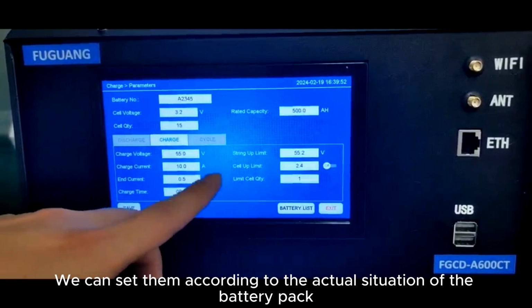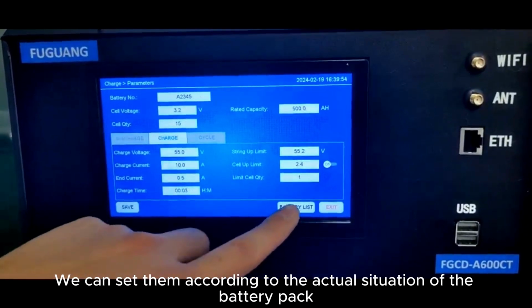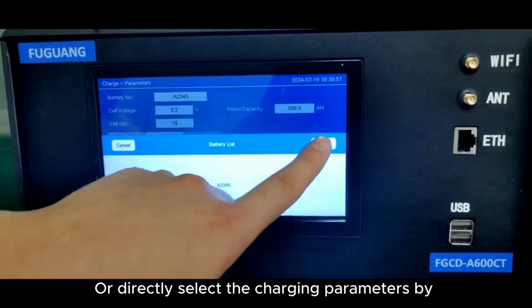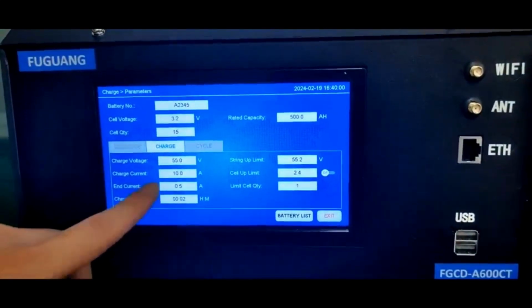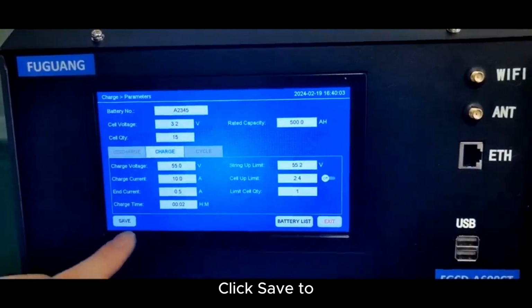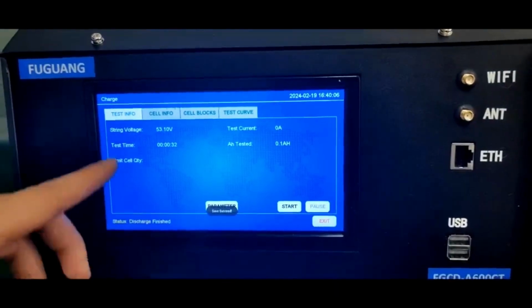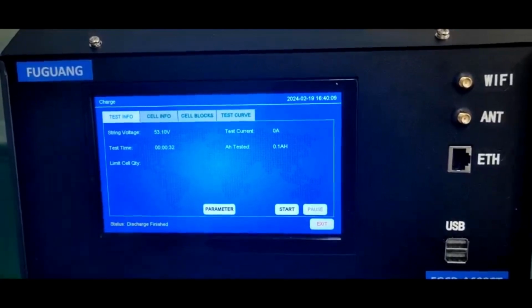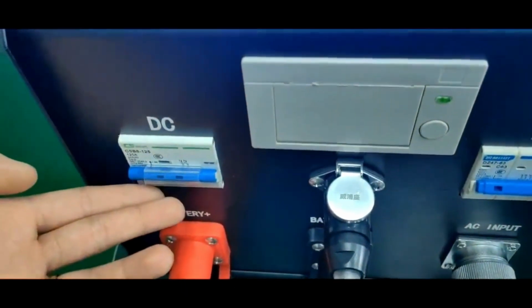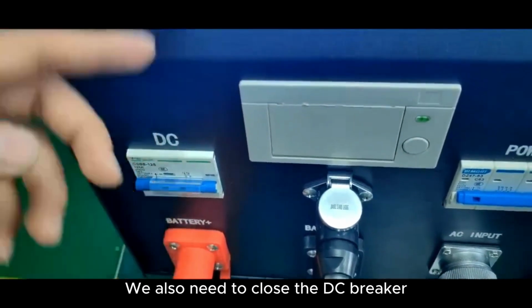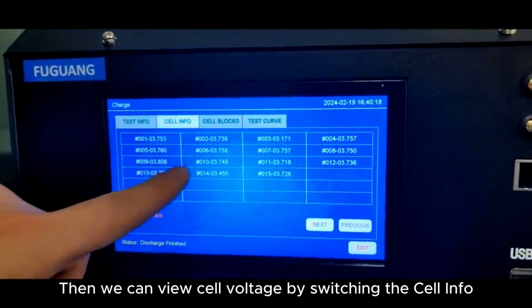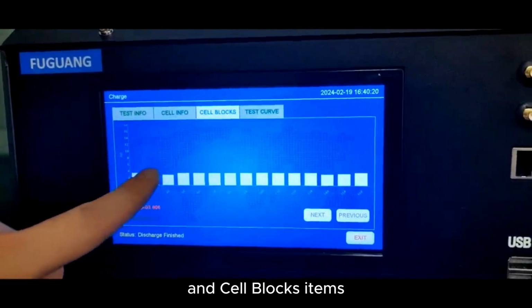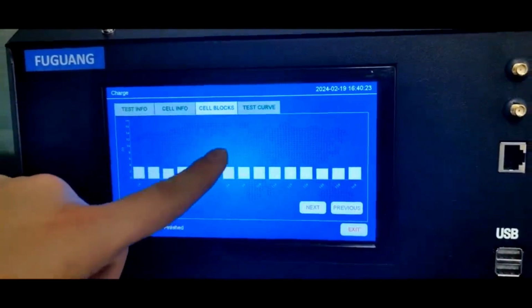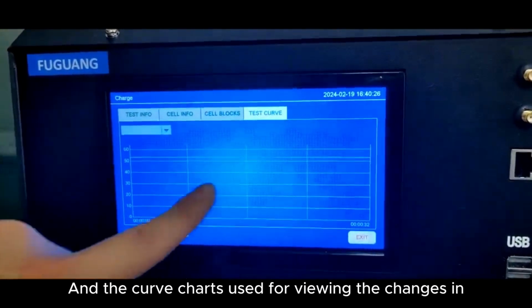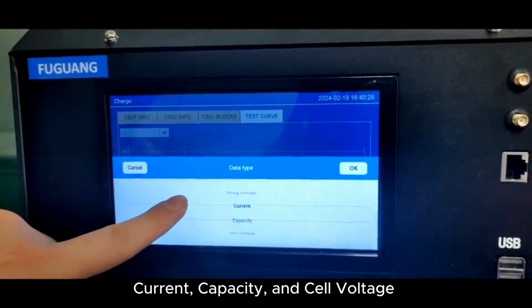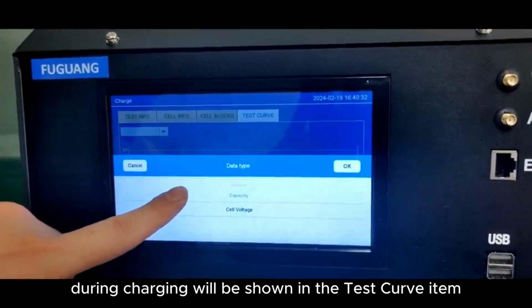We can set them according to the actual situation of the battery pack, or directly select the charging parameters by clicking the battery list. After setting parameters, click Save to enter the charge test page. Before starting the test, we also need to close the DC breaker. Then we can view cell voltage by switching the cell info and cell blocks items, and the curve charts used for viewing the changes in string voltage, current, capacity, and cell voltage during charging will be shown in the test curve item.